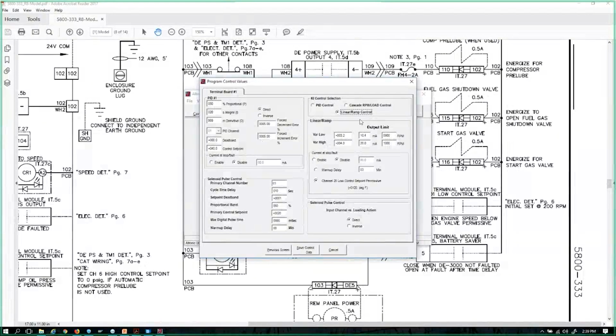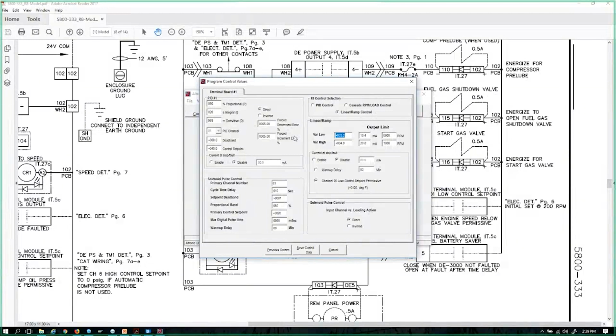And with the linear ramp control, we get 2 targets. So let's keep going based on 40 pounds for our maximum suction pressure and 10 pounds for our recycle valve, even though we just in essence kind of took off our recycle valve by switching over to linear ramp. But let's follow this model. High variable: any pressure greater than 30 psi, I want to put out 20 milliamps and run full speed.